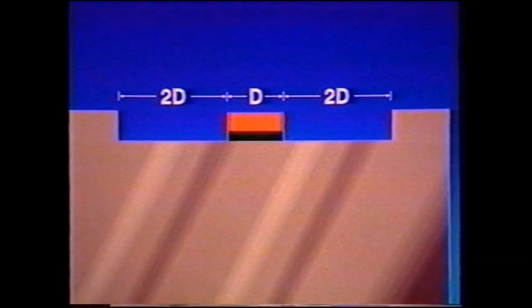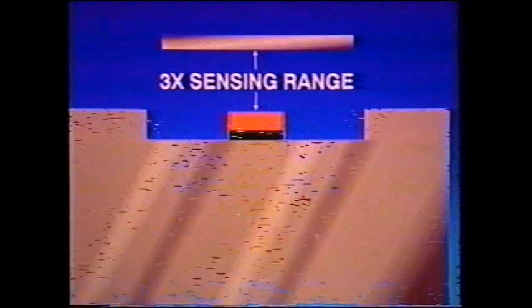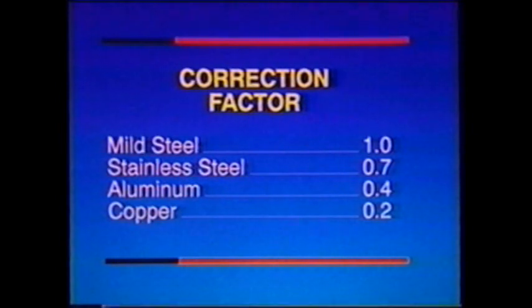If there is metal along two sides, keep it at a distance of 2 times the width of the active face. For all units, tubular or rectangular, keep any metal in front of the switch at a distance of 3 times the sensing range. These guidelines are used when the metal is steel. Remember that other metals reduce the sensing range and will have a correspondingly smaller effect on side sensing by a non-flush switch.